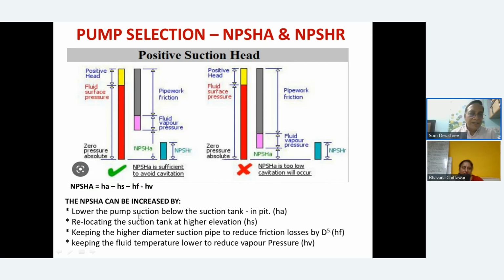Now, how can NPSH A be changed? Because R is the pump's requirement, and A, the available, is your side, by changing the configuration. How can we do this? NPSH A can be increased by lowering the pump suction below the suction tank. So you have a tank at zero, but you dig a pit and put the pump inside the pit. Now you have a positive head, so the suction head is increased. Or you relocate the suction tank at a higher elevation.